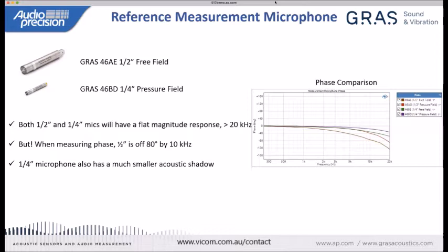The other thing is, of course, the 1/4-inch microphone is just physically smaller, and that means that I can physically put it closer to the microphones under test without interfering with that sound field.